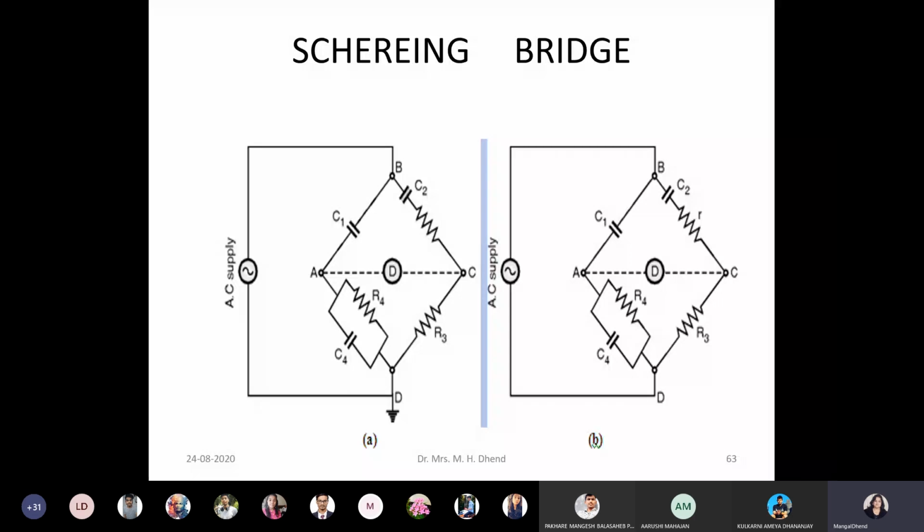Because if we do not check dielectric loss periodically, then day by day, due to aging and use, the dielectric loss may become very large, meaning our tan delta will become very large, and a day will come when it will immediately flash over. Breakdown will take place, because if dielectric loss is more, heat produced in the material will be more, and due to the heating the material will degrade and get damaged, and then a disaster or hazardous thing can happen. So we have to be careful that tan delta is within the limit. Now for measuring tan delta, we will use the Schering bridge. This is the scientist's name, Schering bridge.